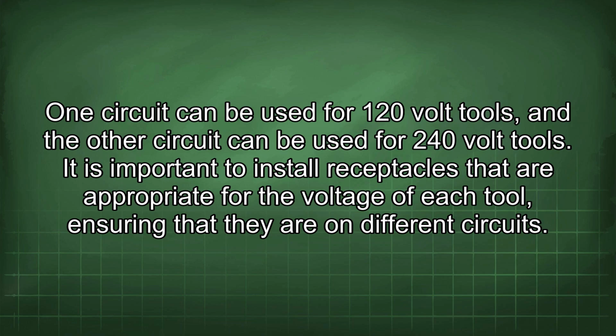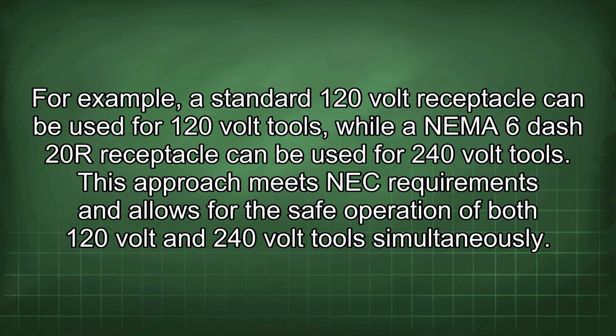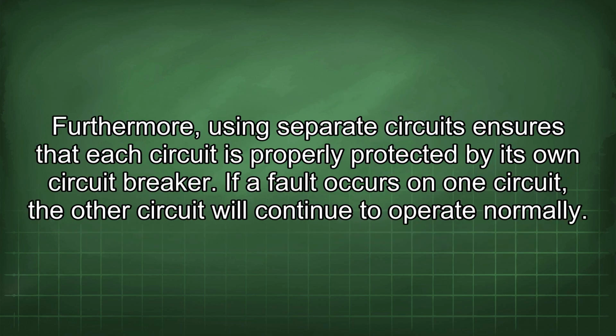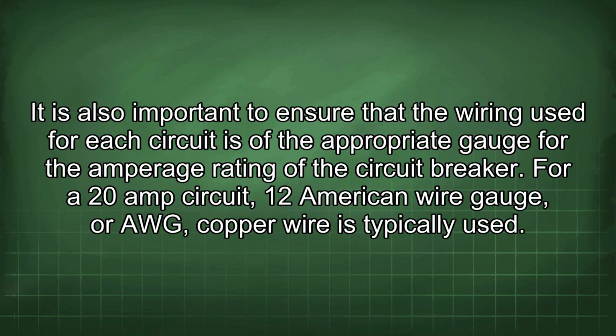For example, a standard 120-volt receptacle can be used for 120-volt tools, while a NEMA 6-20R receptacle can be used for 240-volt tools. This approach meets NEC requirements and allows for the safe operation of both 120-volt and 240-volt tools simultaneously. Furthermore, using separate circuits ensures that each circuit is properly protected by its own circuit breaker. If a fault occurs on one circuit, the other circuit will continue to operate normally. It is also important to ensure that the wiring used for each circuit is of the appropriate gauge for the amperage rating of the circuit breaker.